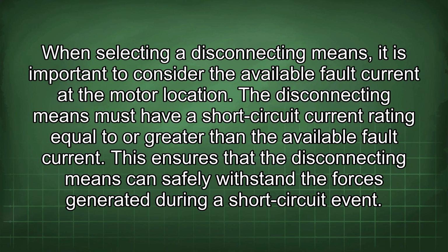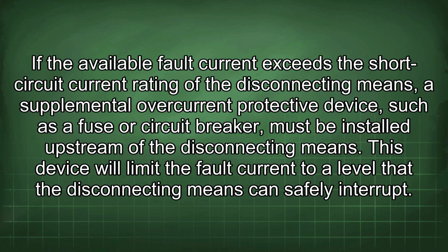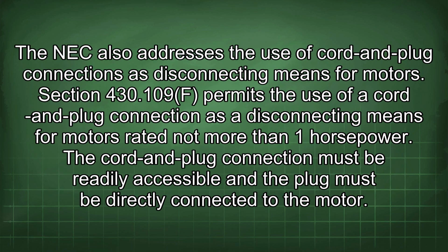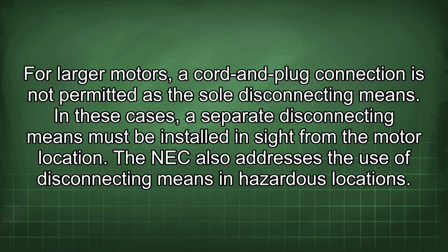When selecting a disconnecting means, it is important to consider the available fault current at the motor location. The disconnecting means must have a short circuit current rating equal to or greater than the available fault current. This ensures that the disconnecting means can safely withstand the forces generated during a short circuit event. If the available fault current exceeds the short circuit current rating of the disconnecting means, a supplemental overcurrent protective device, such as a fuse or circuit breaker, must be installed upstream of the disconnecting means. This device will limit the fault current to a level that the disconnecting means can safely interrupt. The NEC also addresses the use of cord and plug connections as disconnecting means for motors. Section 430.109F permits the use of a cord and plug connection as a disconnecting means for motors rated not more than 1 horsepower. The cord and plug connection must be readily accessible and the plug must be directly connected to the motor. For larger motors, a cord and plug connection is not permitted as the sole disconnecting means.